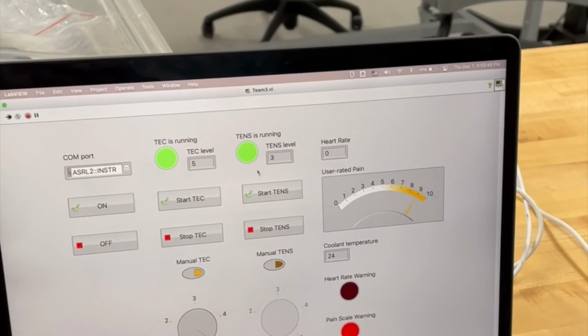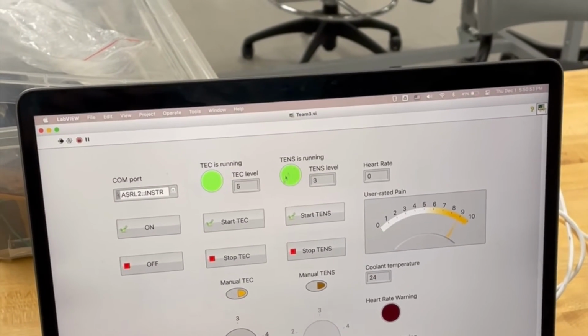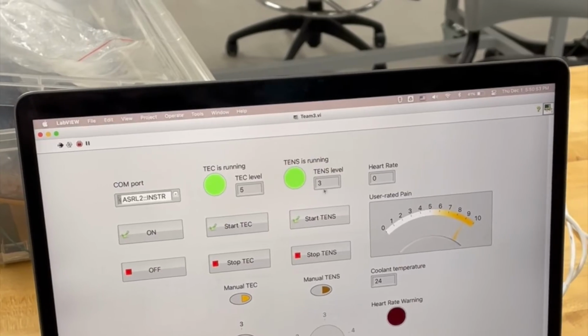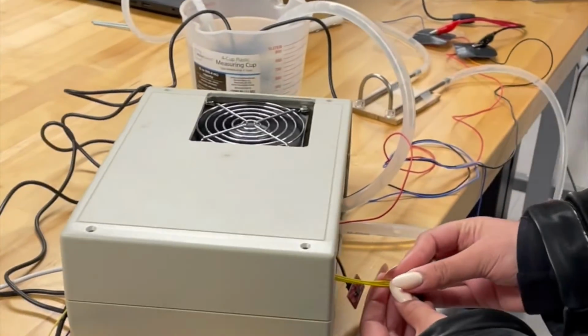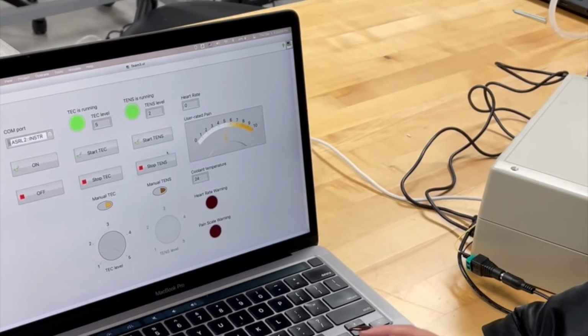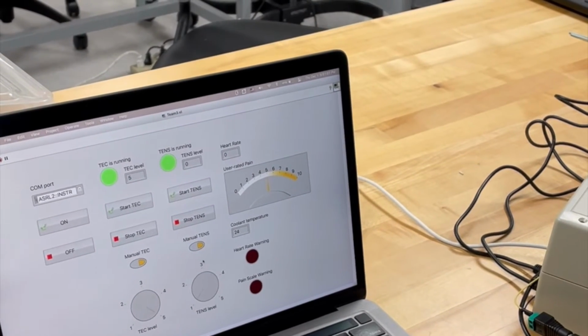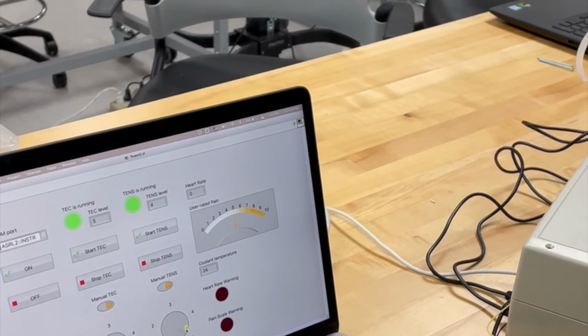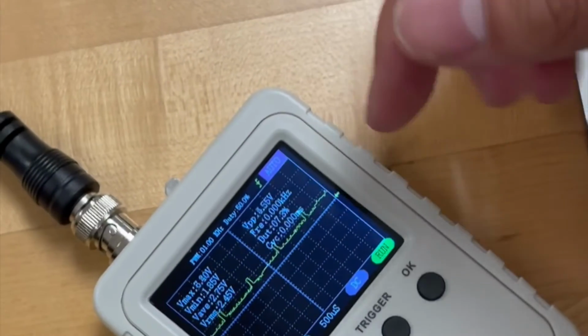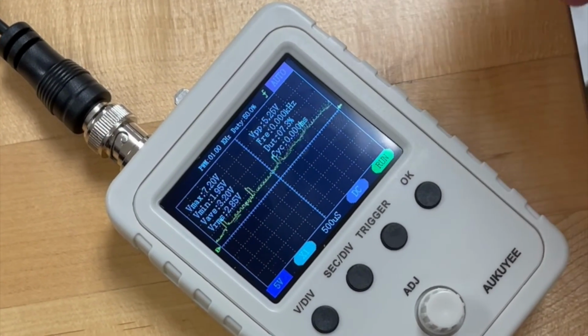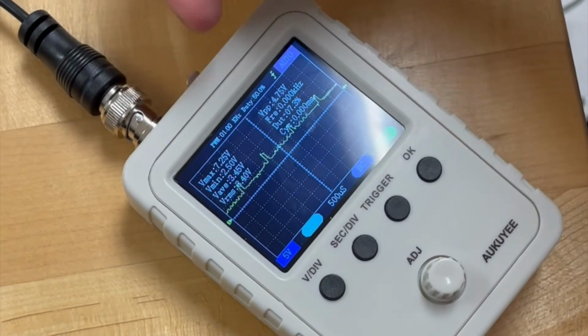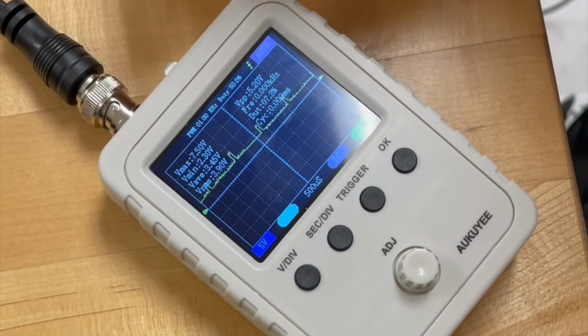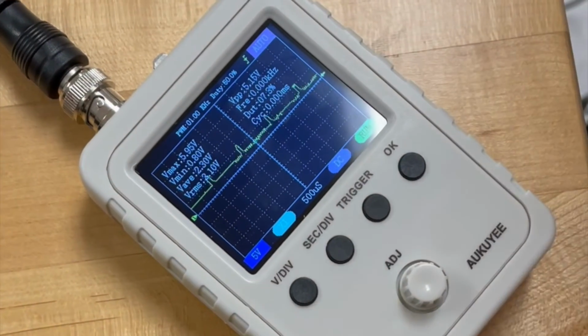And all of that is the same for TENS. So we can turn on TENS, which indicates to the physician through this light that it's on. We can turn it off. The level is controlled by the pain rating and by the heart rate. And we can also switch into manual mode, which gives us the option of changing it through the dial. And then over here, you can see the TENS output with these two electrodes. And then in the oscilloscope, we're reading the signal that is coming out from our TENS circuit. So you can see we have square waves of a certain pulse width, which should be 175 right now.